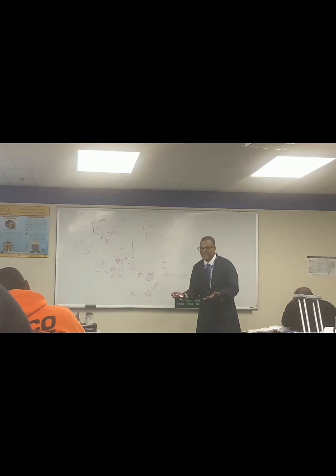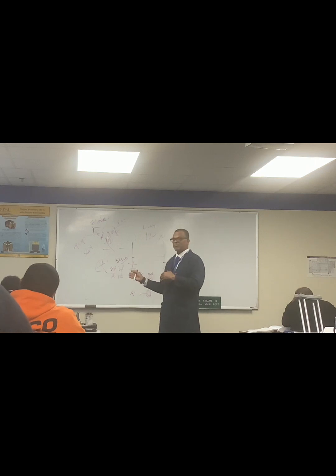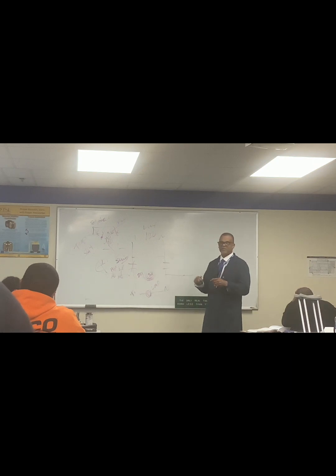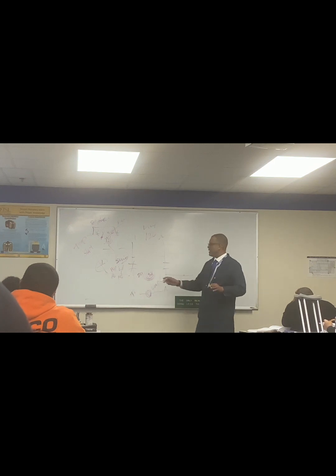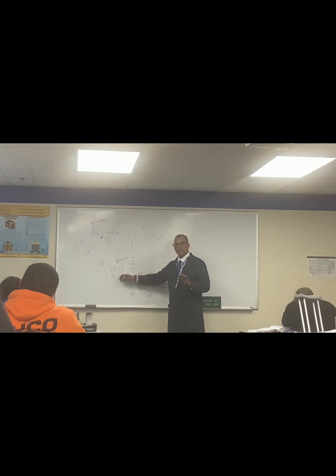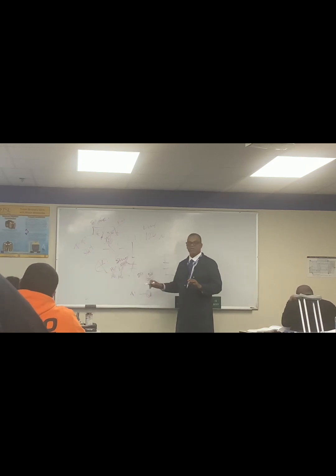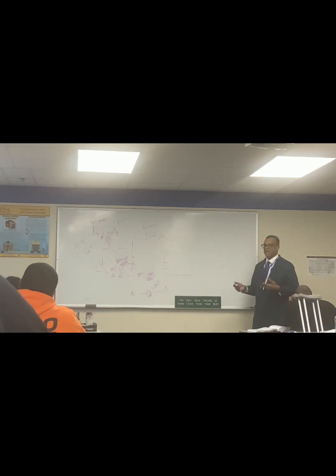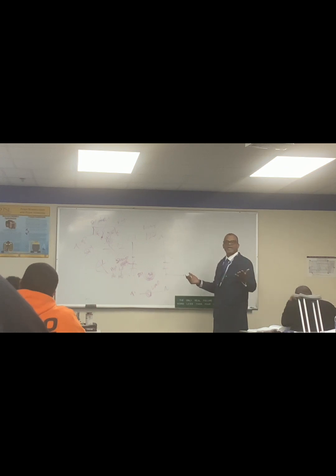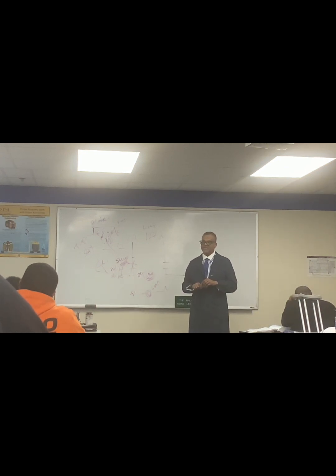So is it overrunning? Is it beyond set point, that we're at 60 and we wanted to be at 78? That could be a different type of sensor problem, but that's control for operation, and the series circuit is control for safety. So series here is also safety, not to ruin the machine. Controls protect, controls operate. They do both. Does that make sense? If it doesn't make sense to you, then I'll talk to you.